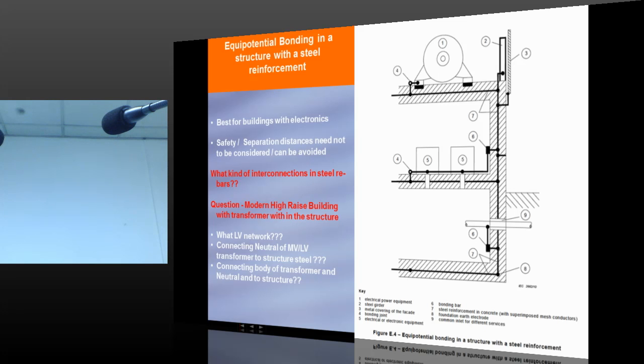this is in the previous slide it was 5. That means the equipotential bonding bar for that particular floor. And from that bonding bar, a PE conductor is running, which is connected to every equipment. Finally, the equipment is also connected to the reinforcement through the other side. So basically, in this kind of an installation, electronic equipment will get a very high protection against LEMP.